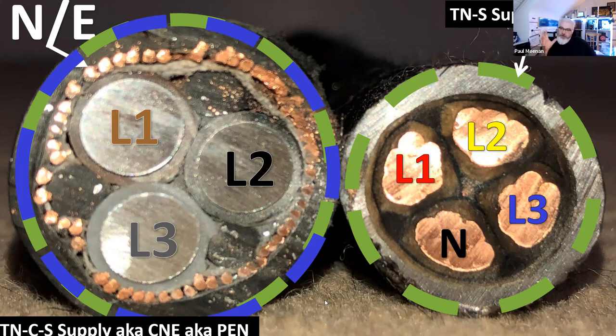But if it's not broken, then I think my mindset, and the easiest way for me to talk about diverted neutrals, is that a diverted neutral is effectively a precursor to a broken PEN. That's the way I look at it. You have current flowing, not necessarily all the way through that combined neutral and earth, because there may be damage. The joints, some of the cores may have snapped, be corroding, may be high impedance. So it's not necessarily the path of least resistance, and it might want to go through other locations.